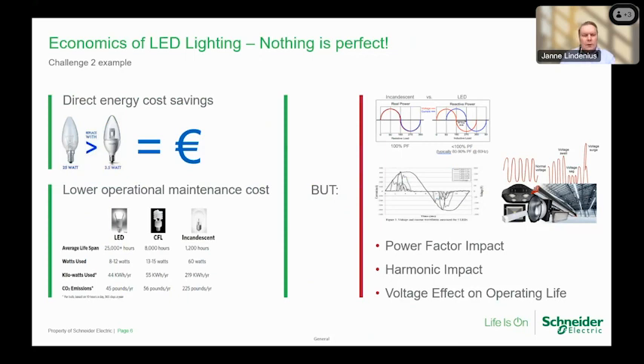Power factor and harmonics, the challenge number 2 example. We have all been seeing the victory of LED lighting. It has a direct energy saving outcome, no doubt about that. But it also brings with it a power factor and harmonic impact. LEDs are an excellent source of trouble regarding these 2 power quality issues. Next slide, please.